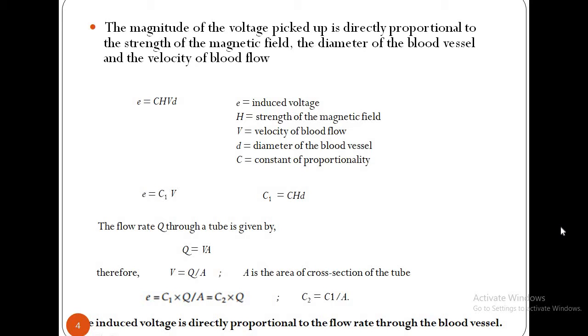Further, the flow rate Q through a tube is given by Q = V A. Therefore, V = Q/A, where A is the area of cross-section of the tube. Hence, E = C1 Q/A, which is equal to C2 Q, where C2 is equal to C1 divided by A. This equation shows that the induced voltage is directly proportional to the flow rate through the blood vessel. The induced voltage picked up by the electrodes is amplified and displayed or recorded on a suitable system. The diameter of the blood vessel is held constant by the circumference of the hole in the probe that surrounds it.